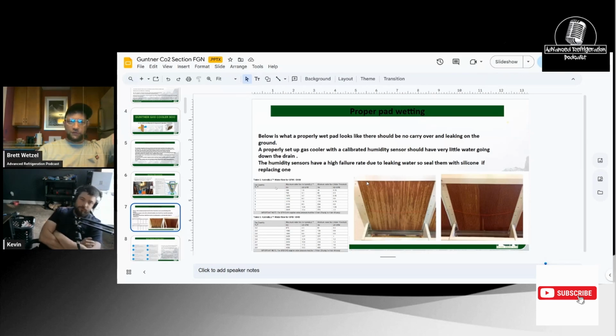So one of the things I was going to do today, which maybe I'll do tomorrow, the one that I'm going to train tomorrow was just started up not too long ago. What I'm thinking about doing is taking a manometer and seeing what the pressure drop is across the pad, and then what the pressure drop is from one side of the coil to the other side of the coil, and seeing what the typical pressure drop should be. Because that would be a good indication to tell you if you've got some kind of internal issue. Yeah, but wouldn't that slightly change with the fan speed?